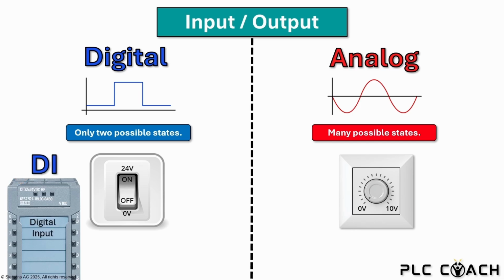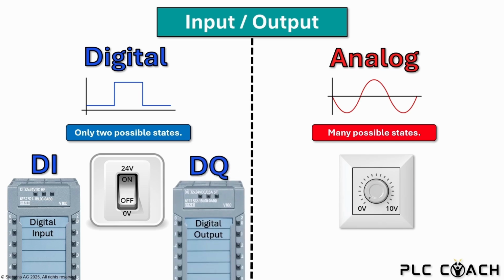DI stands for digital input. You can connect 32 discrete sensors to this module which supply a 24 volt signal. DQ stands for digital output. You can connect 32 discrete actuators to this module which require a 24 volt DC signal. For example, 32 contactors and relays.